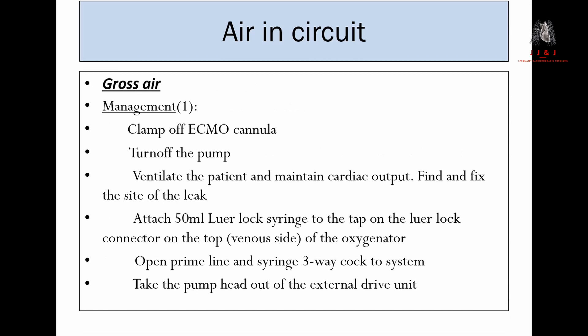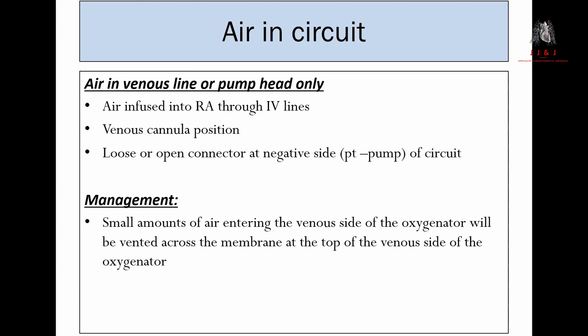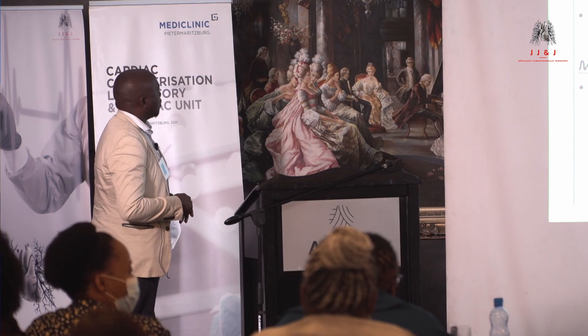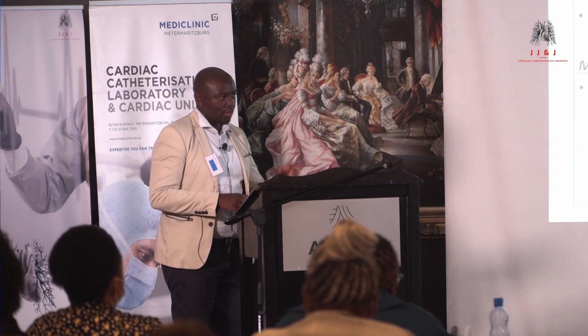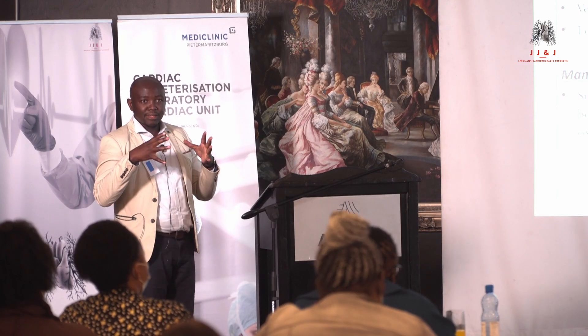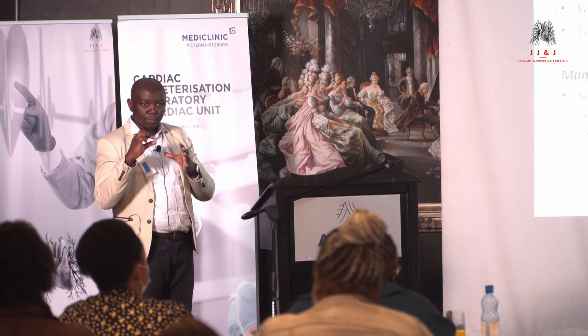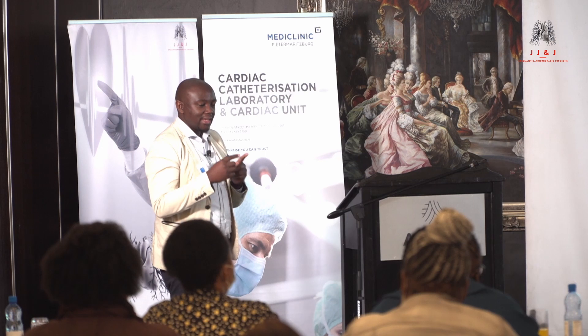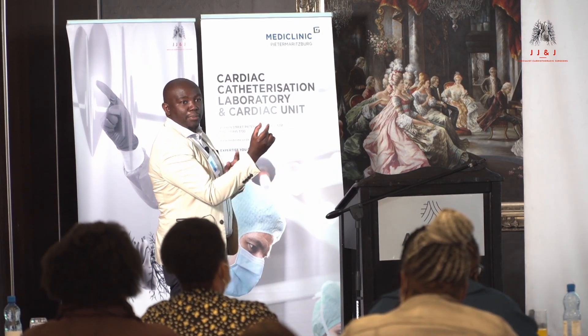Looking at air on the venous line and pump head, we consider three possibilities: air infused into the right atrium through IV lines, which is highly unlikely but possible; venous cannulation and positioning; and loose open connectors exposed to negative pressure. If a small amount of bubbles enters the system, the safety mechanism will alarm saying there is air in the system. If bubbles are too big, it becomes an airlock — at 10 ml or more, the pump will actually stop.